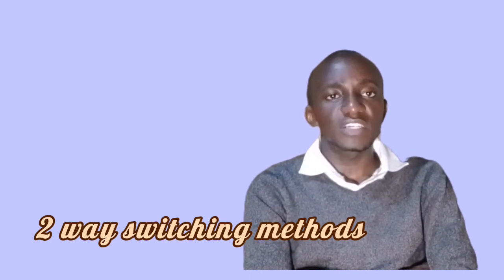And a two-way switching method is where a single lamp or a variety of lamps are controlled from two positions, and we use switches that we call two-way switches. Just like we have a 1-gang one-way switch, 2-gang one-way switch, 3-gang one-way switch, 4-gang one-way switch, we also have a 1-gang two-way switch, 2-gang two-way switch, all the way to as many gangs as possible. So a two-way switch has 3 terminals.